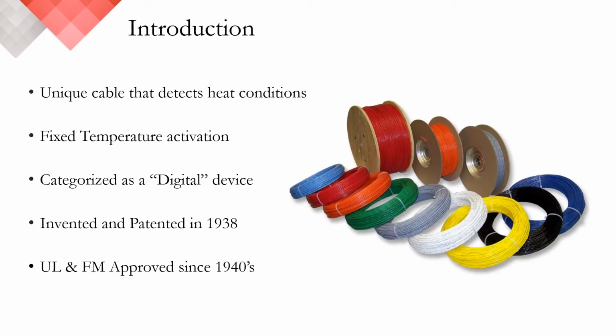We'll begin with a quick introduction. Protectowire linear heat detectors are a series of fixed temperature devices. Their unique design enabled their use in several challenging applications where conventional detectors simply can't reach. Except for fiber optic, Protectowire linear detectors are categorized as digital devices, which is simply to say the conditions of the device are either on or off. The first linear heat detectors were invented back in 1938 by Gerald Holmes, the founder and original owner of Protectowire, and has been listed with both UL and FM since the 1940s.